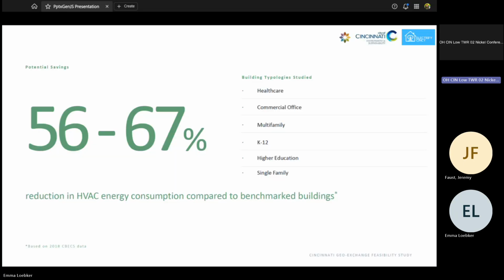In general, what we found and what you'll find in the report is we looked at several building typologies and tried to understand, in terms of impact, what kind of energy cost savings, energy reduction, and emissions reduction performance we could achieve with geo-exchange systems. Looking at legacy equipment and industry benchmarks for how buildings typically perform, and then overlaying how they could perform with geo-exchange systems applied, in general we found that within HVAC energy consumption, these buildings could achieve 56 to 67% energy reduction - a very significant reduction in total energy use.